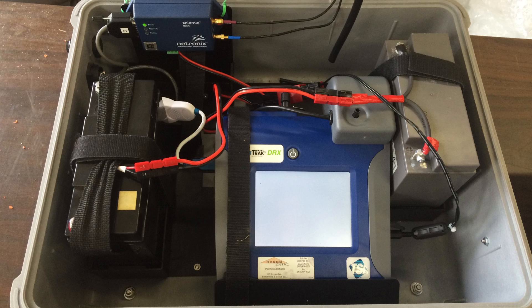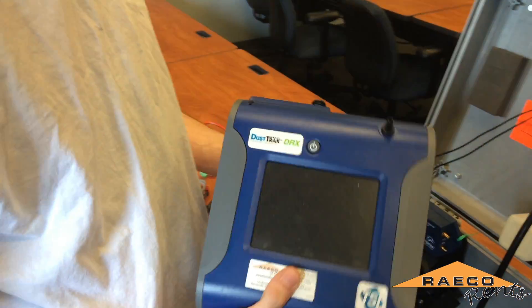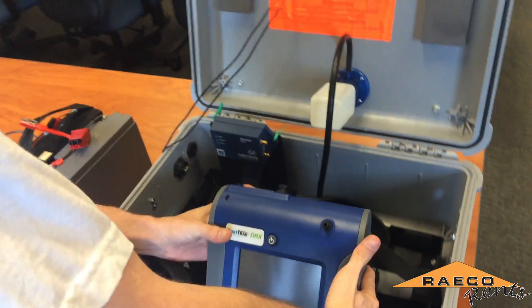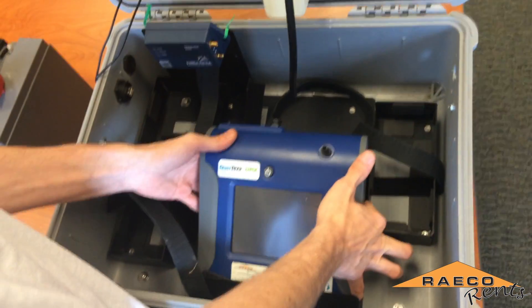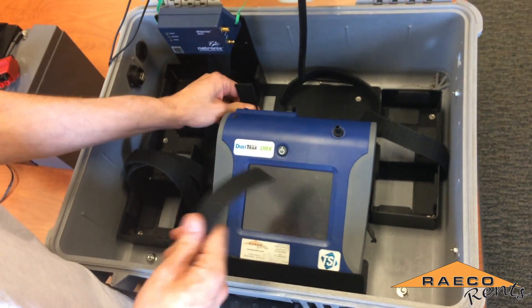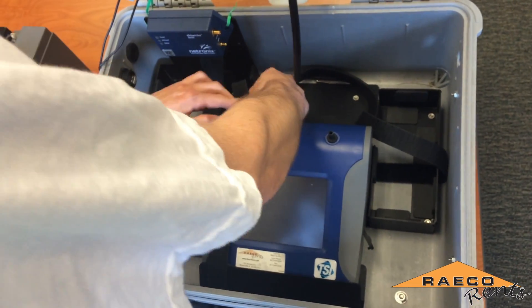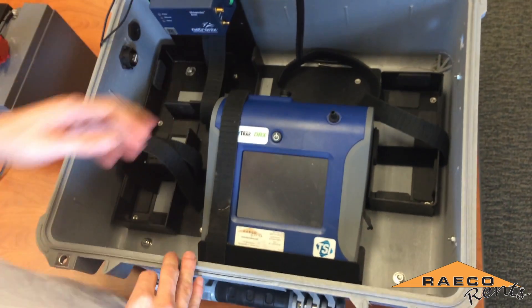In setting up the DustTrak enclosure, the first thing we'll do is take our DustTrak — in this case the DRX model — and we'll set that in the slot on the enclosure case. That straps down with a velcro strap. You want to just make sure it's nice and tight so it can't slide around.